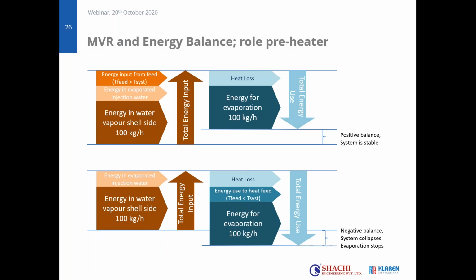There is also a second reason why the same can happen. That is because the preheater might not function. As you see at the top, normally I get energy from the preheater, but if I have a preheater that is too much fouled or is not functioning as it should, and my feed temperature is lower than the system temperature, then I also need energy to get this feed back to system temperature before evaporation can occur. So on the left side, I lose an energy input, and on the right side, I get an additional energy loss or an energy use. And that could lead to the same system instability. So meaning that I have a negative balance and the system can collapse, evaporation will stop.